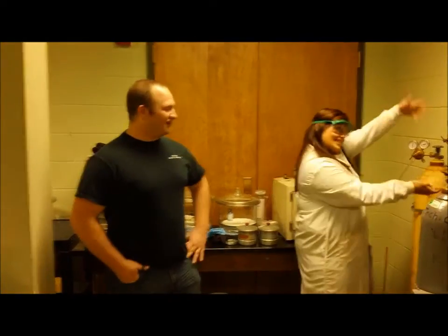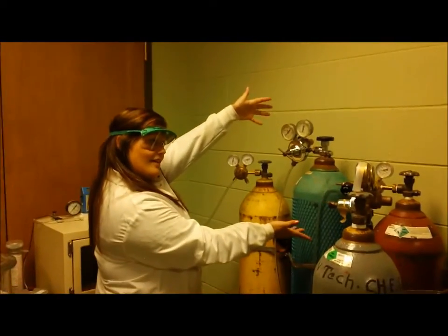In preparing the DSC, you need to make sure the argon is on and connected to the DSC itself, running at approximately 30 millimeters of mercury. You also need to make sure everything is on and operational. The DSC needs to be on by the green light and ready by the yellow light. The chiller also needs to be on to keep the DSC steady. The computer needs to be on for data analysis and logged into as a lab user.